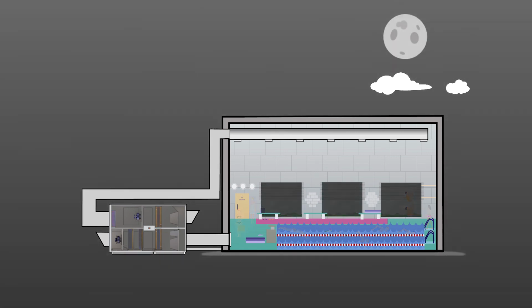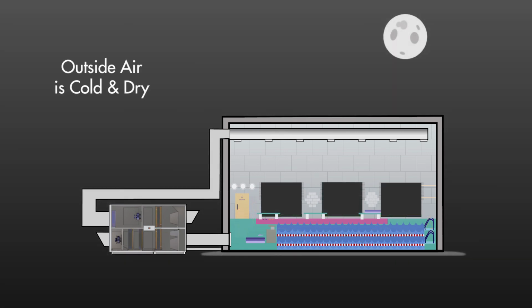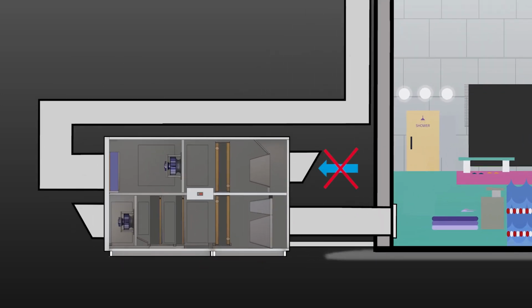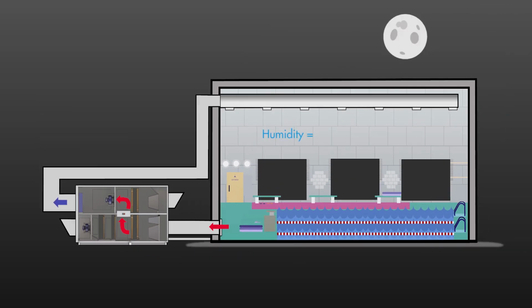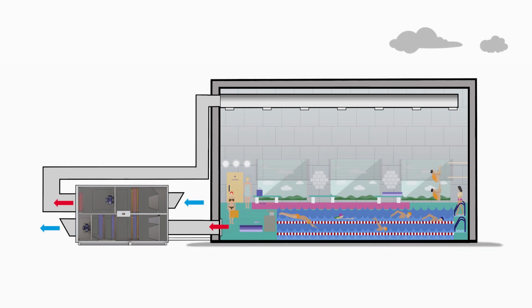And so, when a pool facility is not in use and the outside air is cold and dry, the PoolPac Plus can use reverse cycle cooling to provide the humidity control instead of fresh air ventilation. In this case, outdoor ventilation air is minimised and replaced with recirculated air, which prevents large quantities of dry air from entering the pool hall and absorbing moisture from the pool surface. Cooling and heating the recirculated air as required allows the indoor humidity to be controlled to a level high enough to limit evaporation from the pool surface, but low enough to limit condensation around the pool hall. Once the indoor pool is about to be occupied once again, the PoolPac Plus switches back to ventilation mode and purges the airborne chloramine from the indoor air.